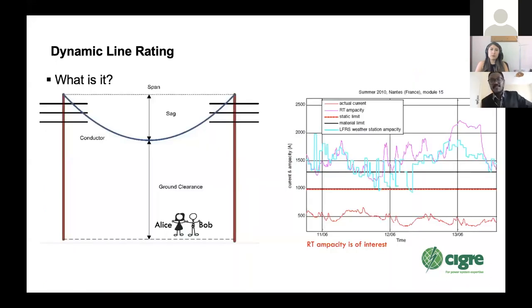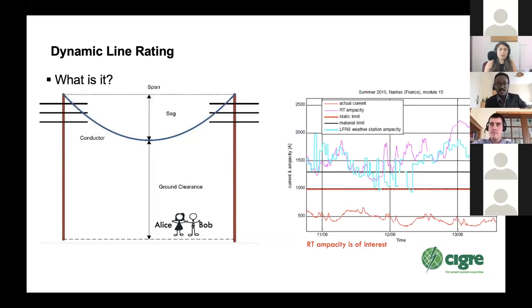So dynamic line rating is a potential solution to the problem of curtailment. And so I'd like to introduce dynamic line rating to you. As you can see in front of me, when overhead lines are designed, they're usually designed with ground clearances in mind. And these ground clearances are legal requirements that are set forth to ensure the safety of the public, Alice and Bob in this example.